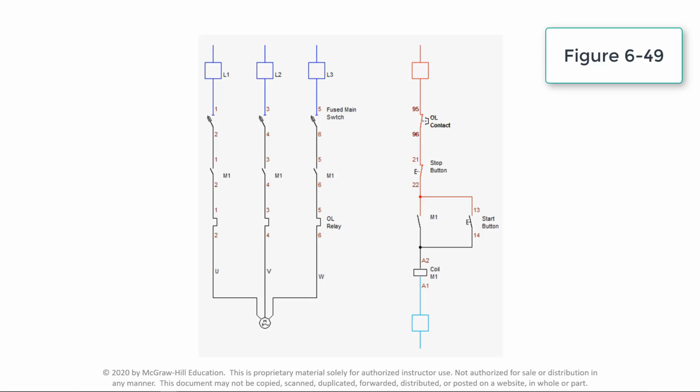The terminals of the IEC auxiliary contacts are marked with a two-digit number. Terminals that belong together are marked with the same location digit, the first digit. The second digit, called the function digit, identifies the function of each contact in this IEC schematic.